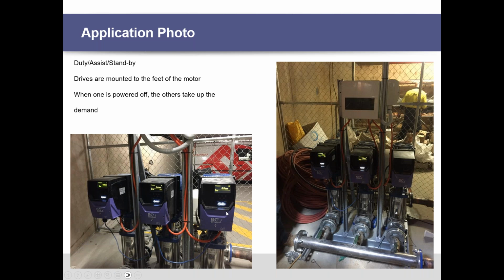So there's an example of a duty assist standby system that we actually did here in Brisbane with one of our pump OEMs. They have a pressure transducer coming from the system into the drive. Then we connect the drives together just with an RJ45 cable, and they work together to ensure that there's always system pressure available. This was in a residential high-rise block of flats or apartments. So if there's low demand, if everybody's out at work, for example, then maybe just one of the pumps will be running. If they need full system pressure, then two of them will be running, and the third one is always in a standby type mode.